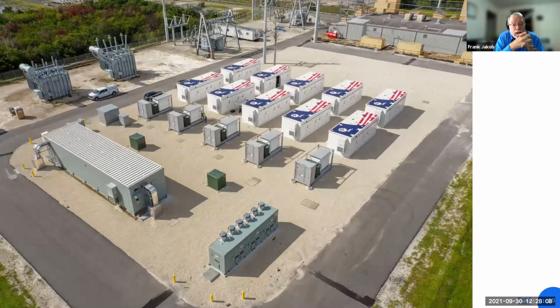Here's an example of a facility Black & Veatch has built. In terms of size, this is about a quarter acre site. There are five of these, each with 2.5 megawatt inverters for a little over 10 megawatts, along with the containers that have the batteries inside them. This facility, nominally 10 megawatts and 4 hours of storage, takes up about a quarter of an acre.